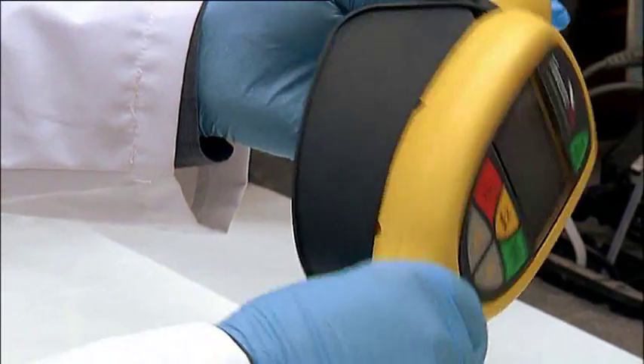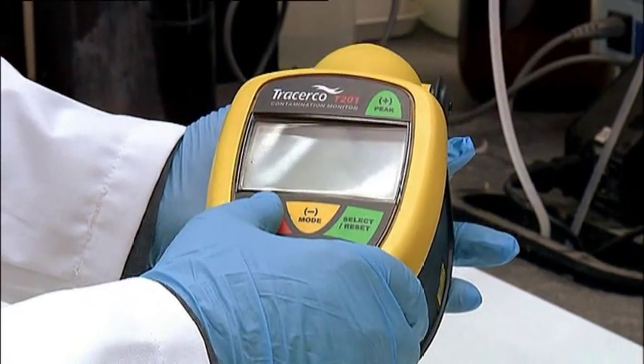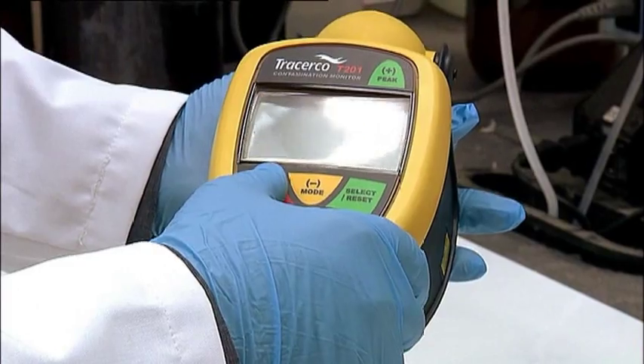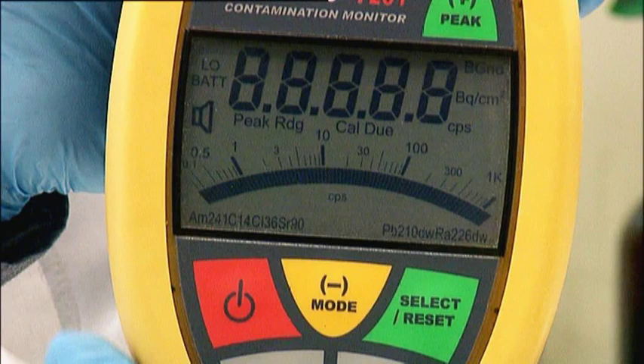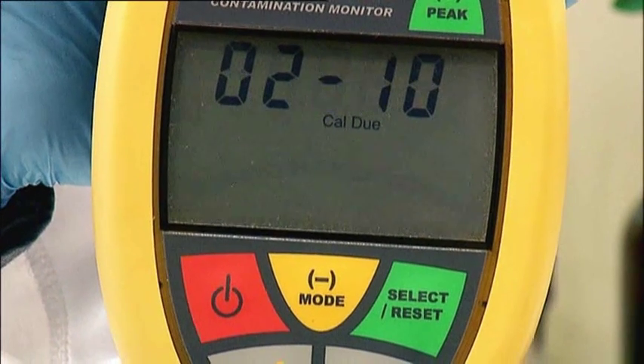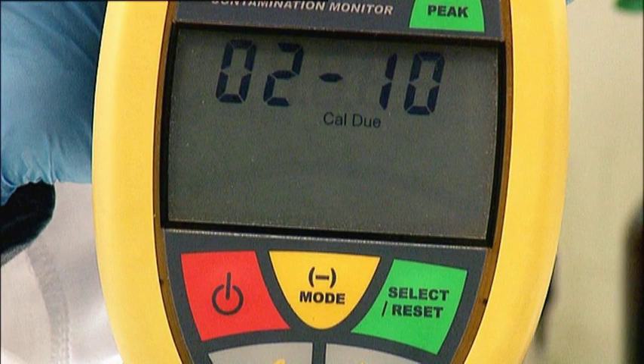The monitor is activated by pressing the red on-off button. When pressed, the screen provides a 2-second test display of all operational parameters and then displays the next calibration due date. This date is automatically reset through the instrument software when recalibration takes place.